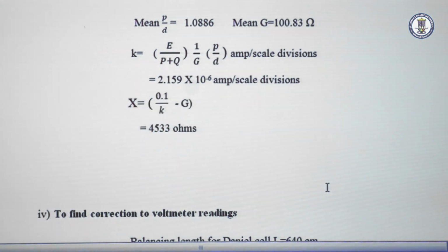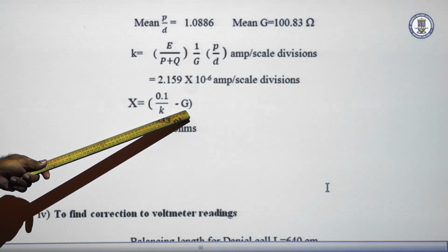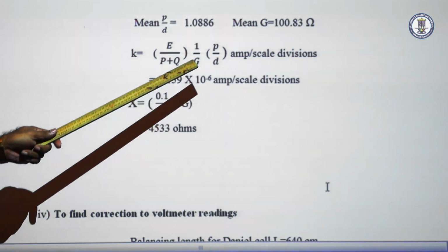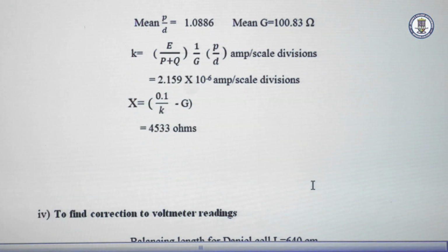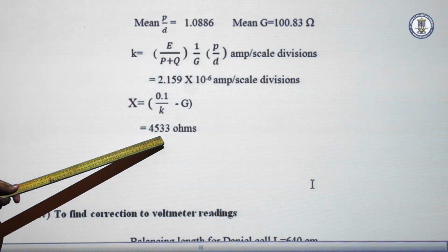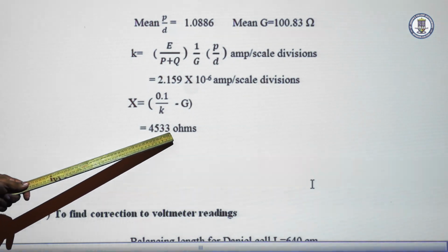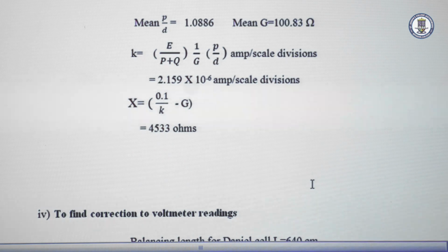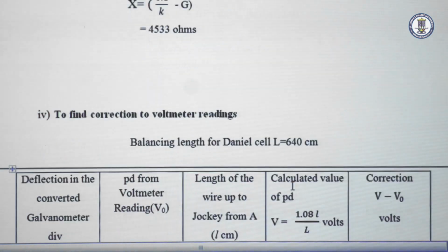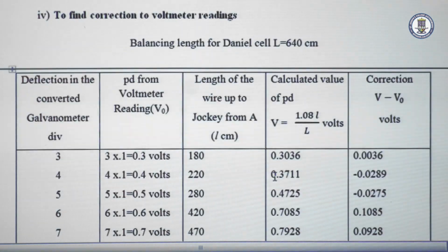P by D is calculated, and we obtain K as 2.159 into 10 to the power of minus 6 ampere per scale division. Now X is calculated using the formula 0.1 by K minus G, that is 0.1 by 2.159 into 10 to the power of minus 6 minus G, where G is equal to 100.83. So we obtain a very high value of resistance, that is X is equal to 45330 ohm. Now this high resistance is connected in series with the galvanometer, and then it is converted to a voltmeter.